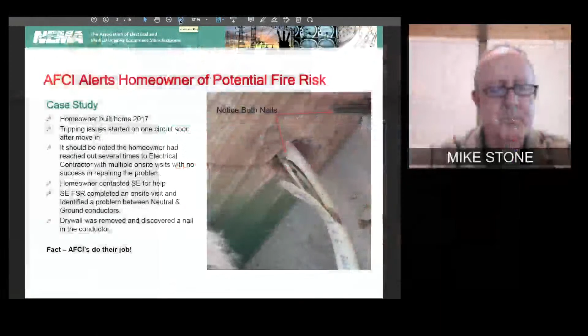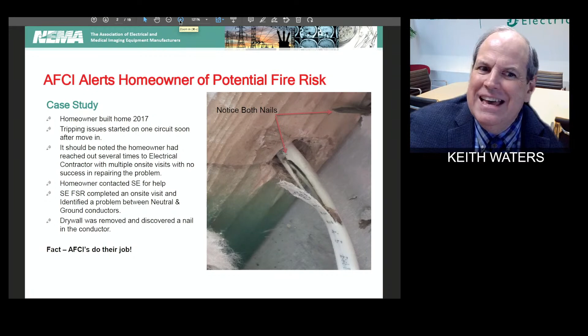But the contractor couldn't figure out what was going on. The homeowner was concerned, the home builder too, so there were multiple visits trying to figure out what was causing the tripping activity. The first thing to understand is that when a breaker trips, there's usually a reason it's tripping, right? That's its job - if it sees a problem, it's supposed to trip, right?